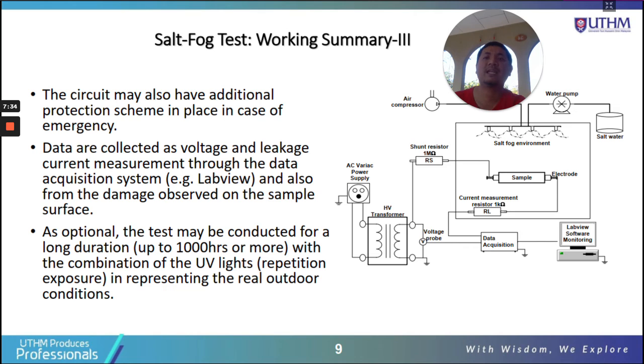All right, so the circuit may also have an additional protection scheme in place in case of emergency. Data are collected as voltage and leakage current measurements. So we measure the leakage current, how much current leaks to the ground here, using that current measurement resistor, and we have the voltage probe here. Besides measuring the voltage and the leakage current, if there is damage on the sample, we have to make observations and report on the damage. And as optional, the test may be conducted for a long duration up to 1000 hours or more with the combination of UV lights. You can expose the test sample to UV lights to represent the real outdoor condition.